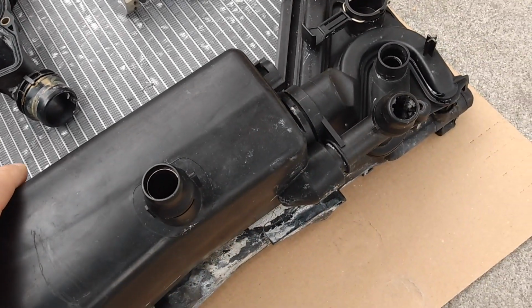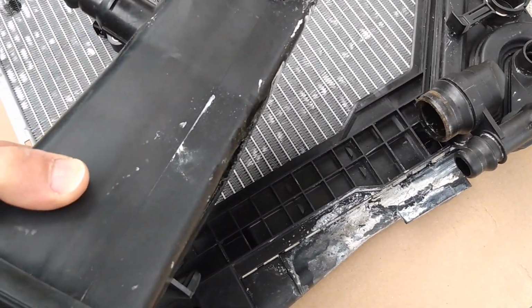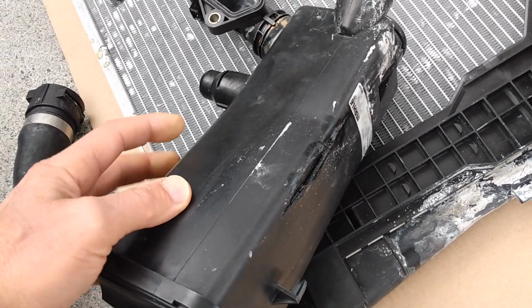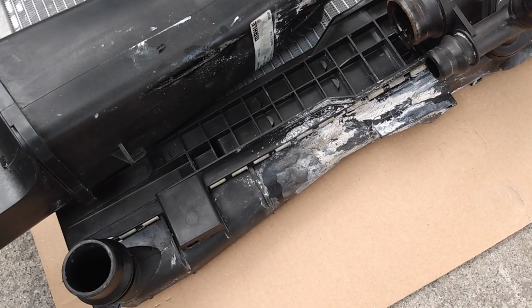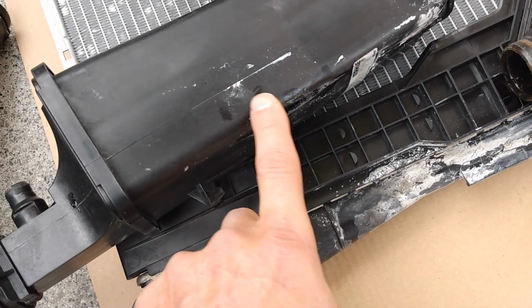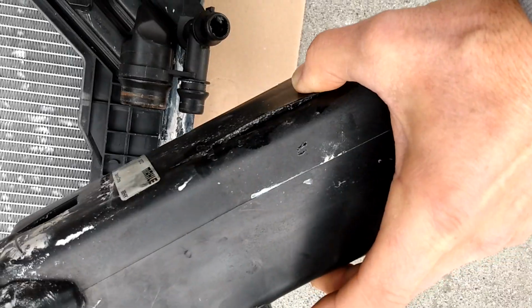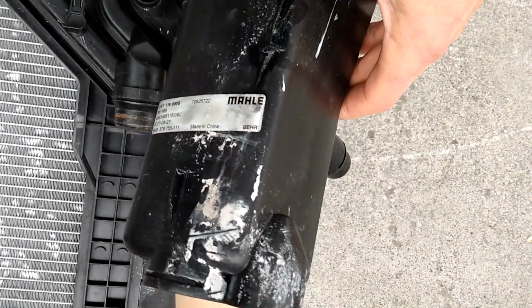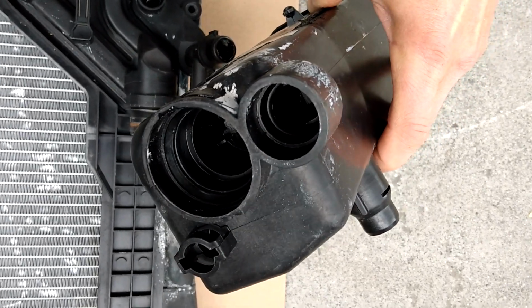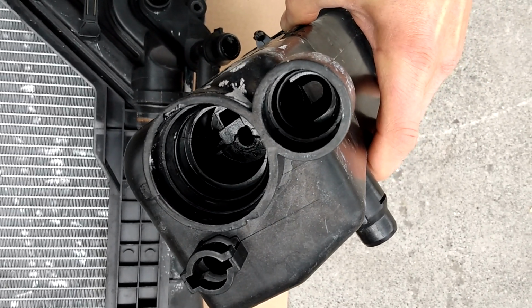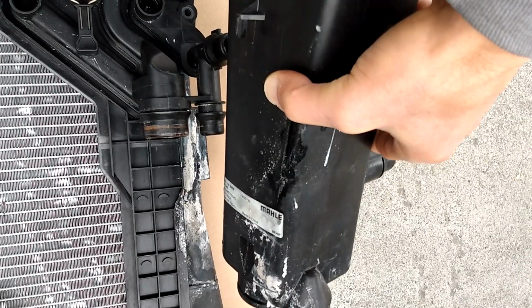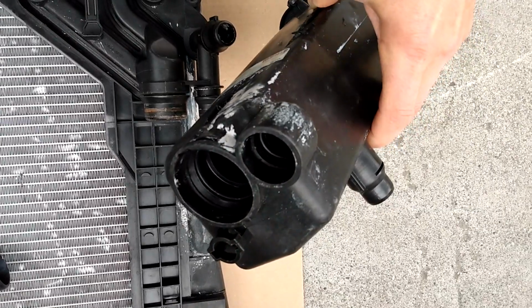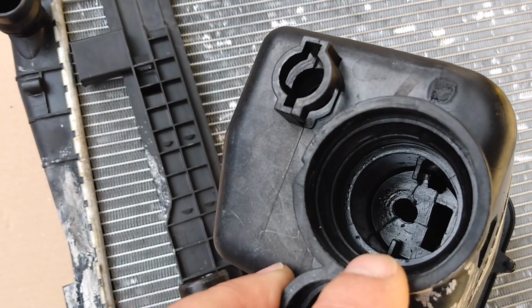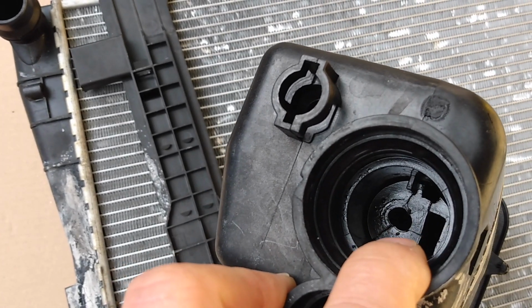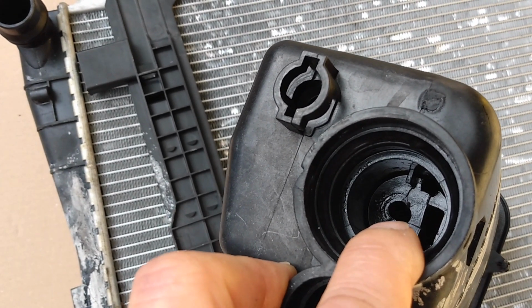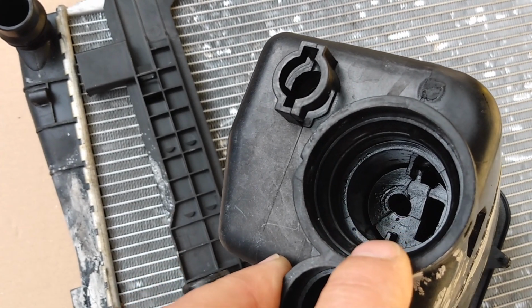When I removed the expansion tank, I discovered there's a split on the expansion tank, and this is actually coming from the split. The split is an indication that there was high pressure in the system, as would be expected if there was a failure in the thermostat. The system would have recirculated very hot water through the expansion tank. You can see some damage.